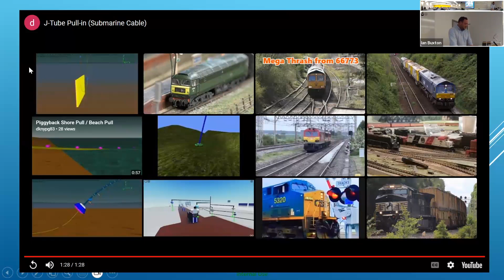Now, joint installation: we can't have 147 kilometers of cable on a ship. It just physically wouldn't fit. So on this project, for example, we're installing 75 kilometers of cable to start with. We then go back to the factory, pick up the additional cable, come back, and we have to joint it offshore. To join an HVDC cable, you allow between 7 and 10 days offshore time to actually physically joint the two systems together. It then has to be tested. Once it's tested, it then gets overboarded by the vessel.